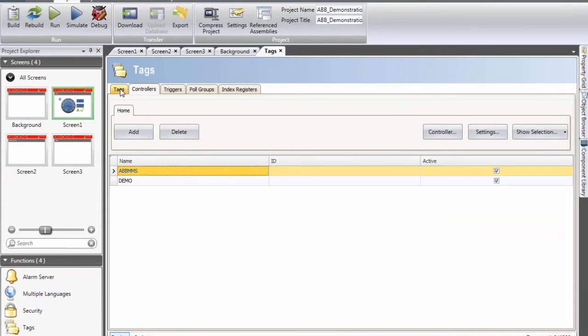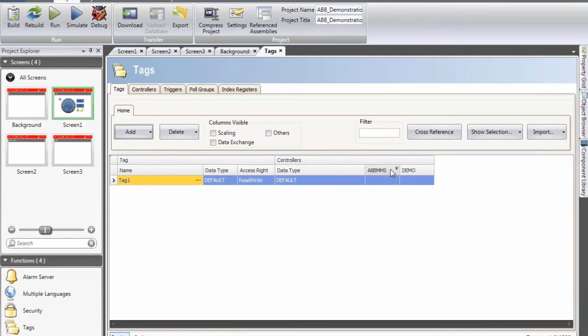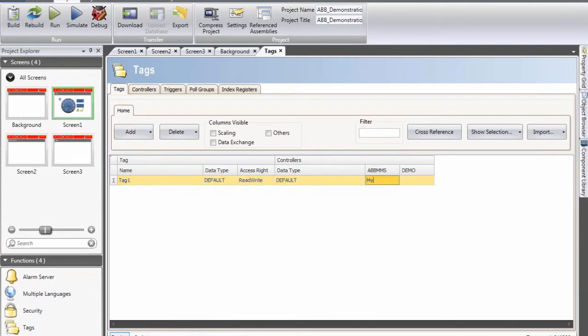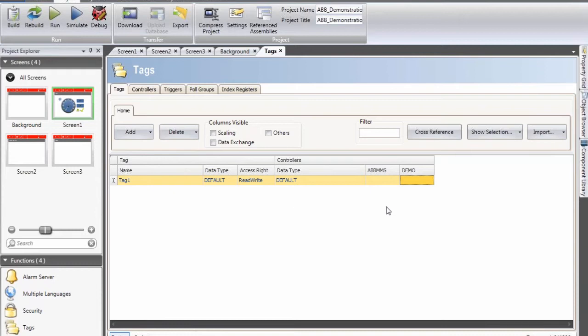I change to the tags column. Now you can see that I have one tag called tag1. It's an internal variable right now because there are no addresses assigned to this tag. I could type in an address manually — in the ABBMMS driver that means I would try to read an access variable called my tag — or if the demo driver uses more traditional addressing, I could write D0 for an integer. There is a syntax check included so that whatever you type in is valid syntax for that driver. However, for the ABBMMS driver it's not necessary to configure tags manually.